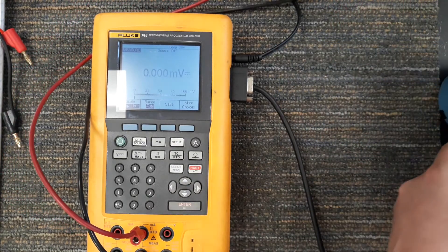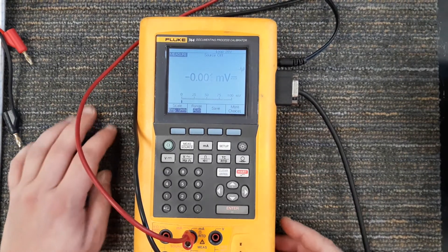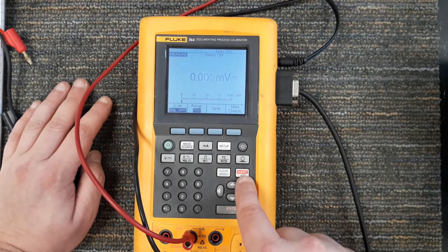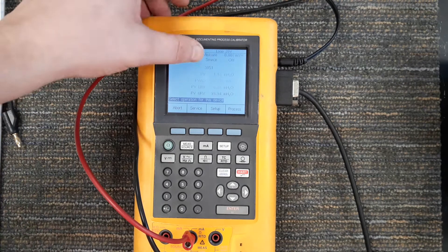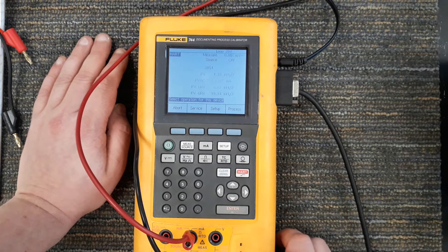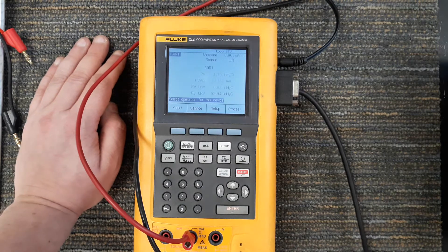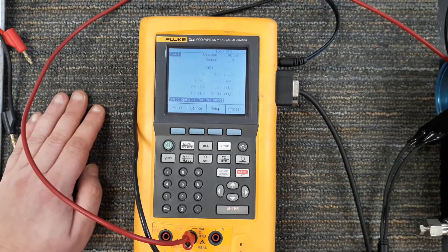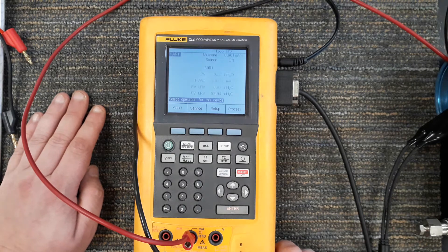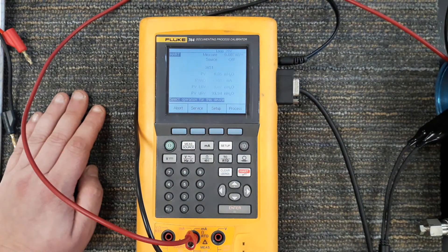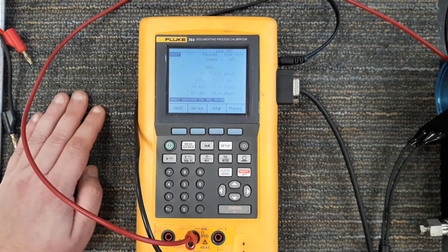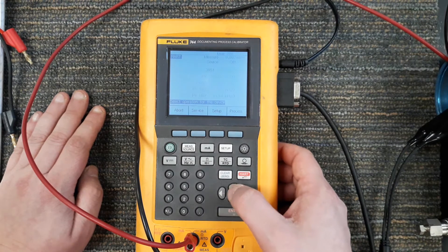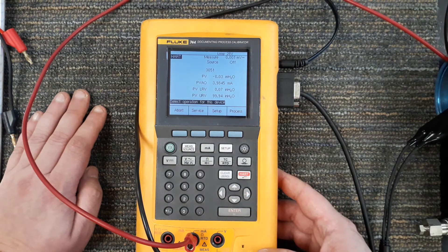I'm going to hit the HART communication button. Searching for a HART device, please wait. It found a 3051 and it's telling me that right now the process variable is reading 1.18 inches of water, probably because I have it sideways. If I lay this so that both pressure diaphragms are on the same plane, it gets a lot closer to zero. The analog output is at four milliamps, my LRV is zero inches, my URV in this case is 99.94, should be probably 100.